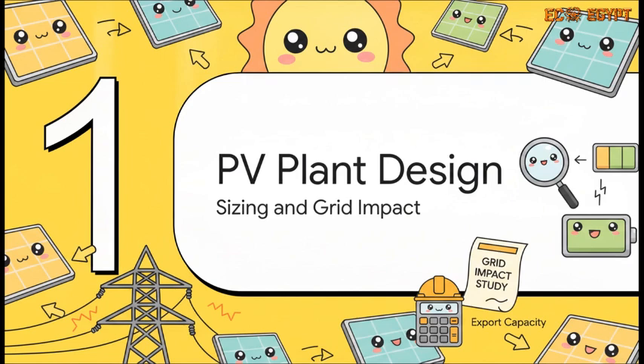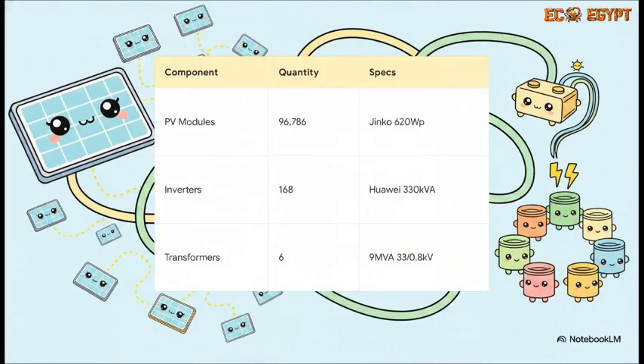Let's kick things off with Part 1, Utility-Scale PV Plant Design. Professional design doesn't just start with how much land you have—it starts with the grid impact study, which dictates our maximum export capacity. Based on those network limits, we size the plant at a massive scale: nearly 97,000 PV modules at 620-watt peak each, feeding into 168 string inverters and 6 9-megavolt ampere transformer stations, all coordinated into a 33 kilovolt medium voltage collector system.